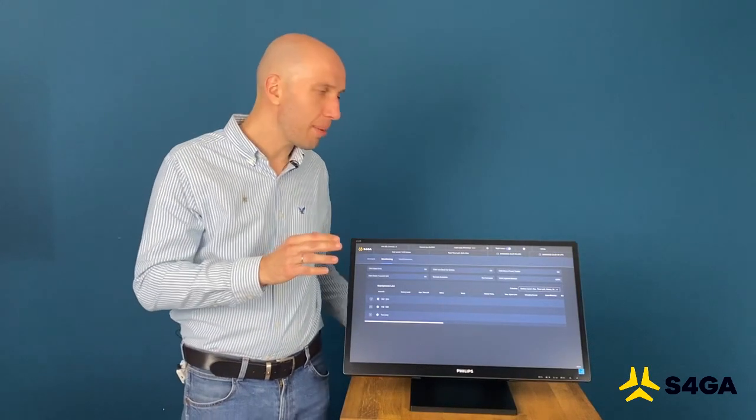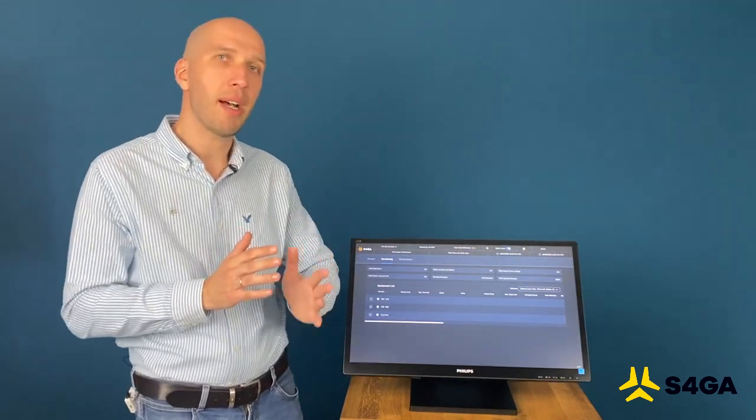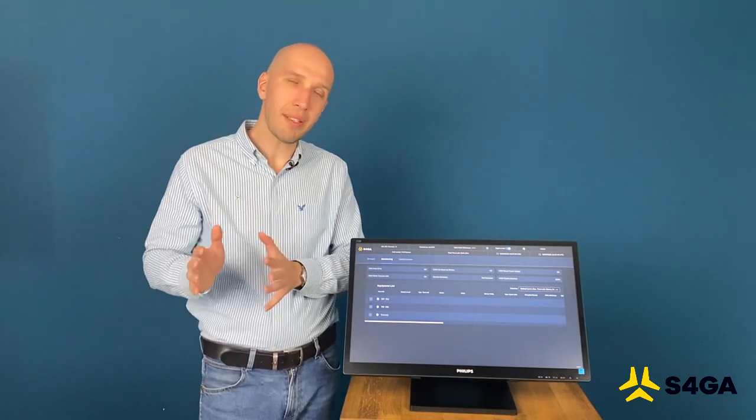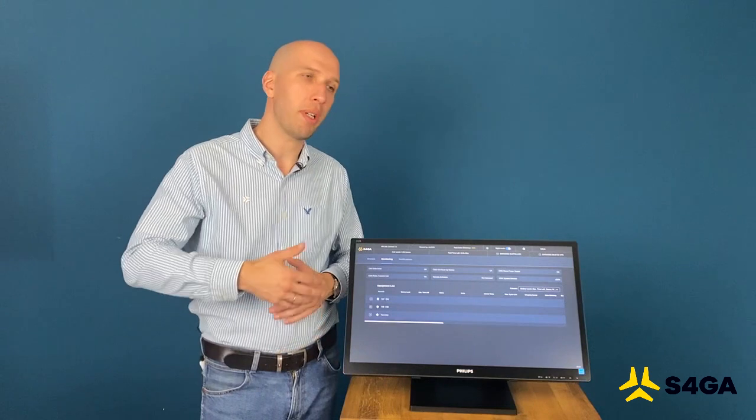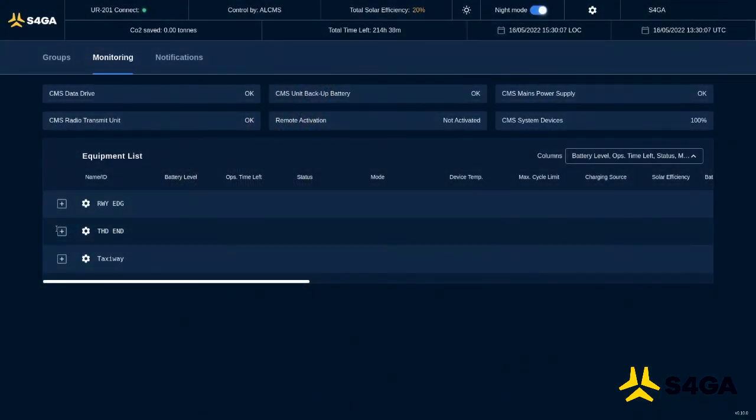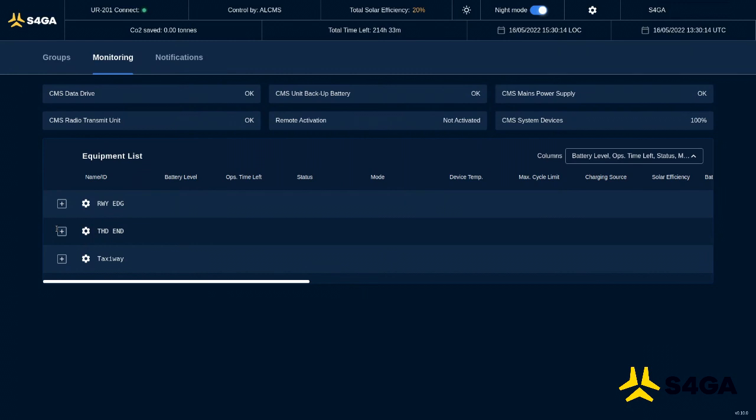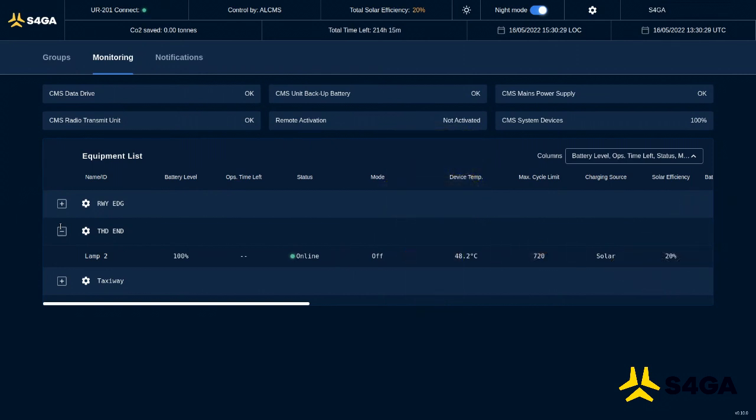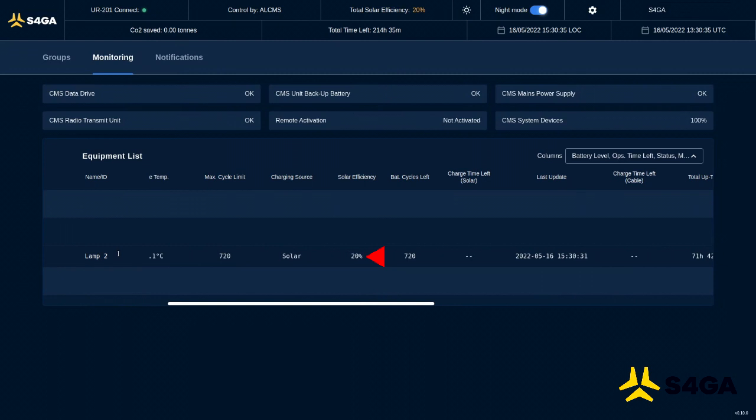So now let's move to the monitoring part of ALCMS. It provides us with information about each individual light. So we can collect data from lights and we can present it to maintenance and technical team. So let's see what kind of data is available to a user for each individual light. You can see there is a group threshold end with lamp number two. Lamp battery level is 100 percent. Light is online, which means there is a communication between control unit and the light itself. Light is currently off. Temperature is almost 50 degrees Celsius. Light is being charged from the solar panel and charging efficiency is 20 percent. Why 20 percent? Well, since battery is 100 percent, the solar charger decreases its efficiency automatically, not to overcharge the battery.